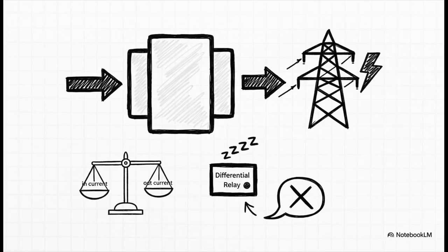Let's say a tree falls on a power line, like miles away. A massive amount of current is now flowing through the transformer to feed that fault. But our differential relay? It sees that the same amount of current is flowing in as is flowing out, so it just says, nope, not my problem, and stays quiet, letting some other device down the line handle it.